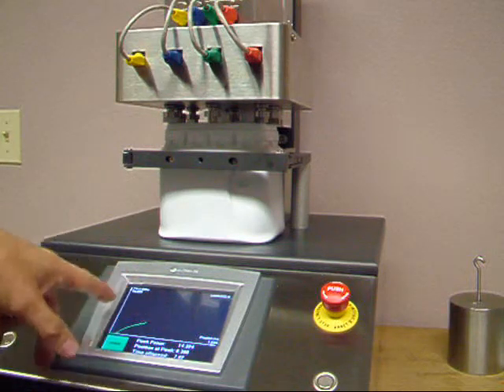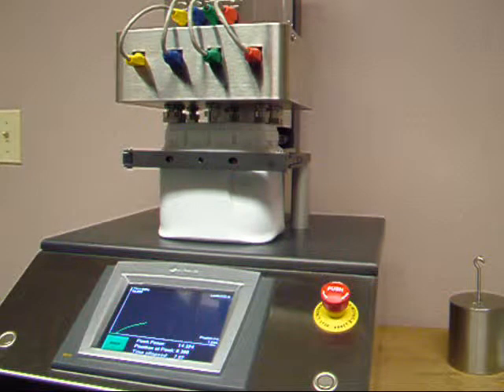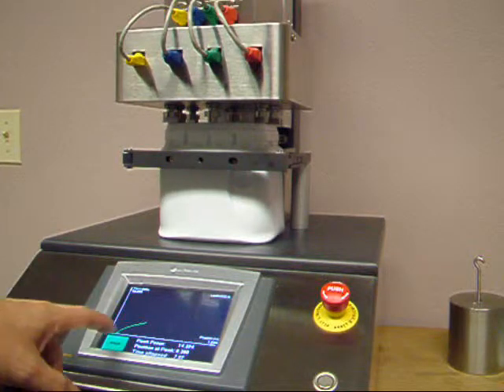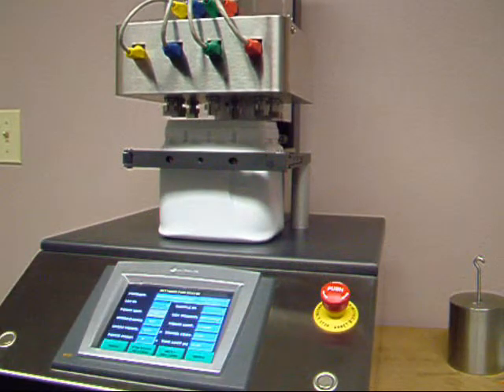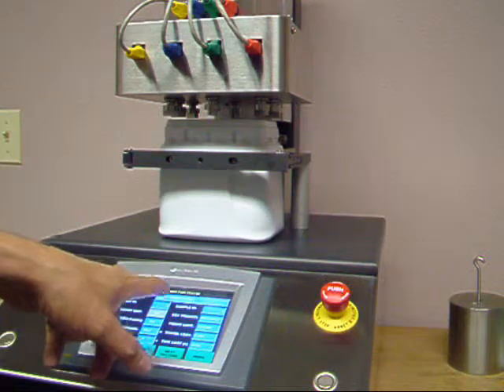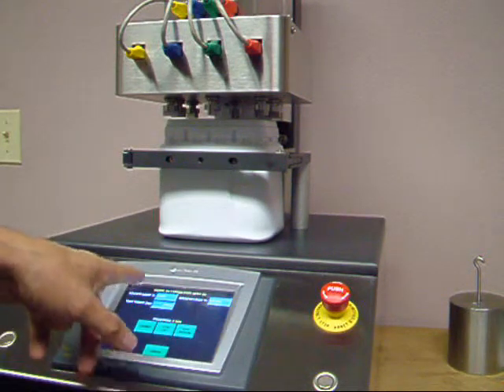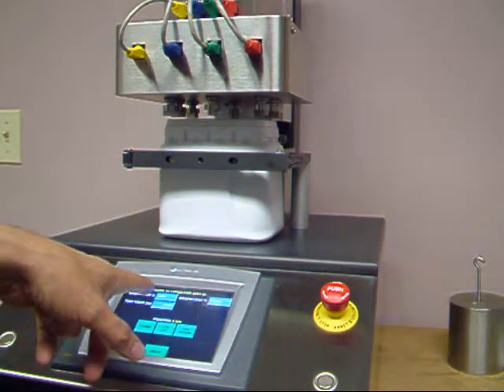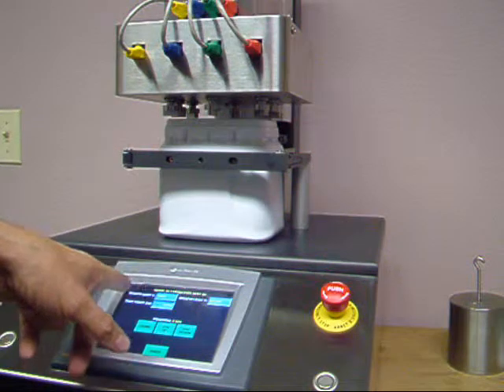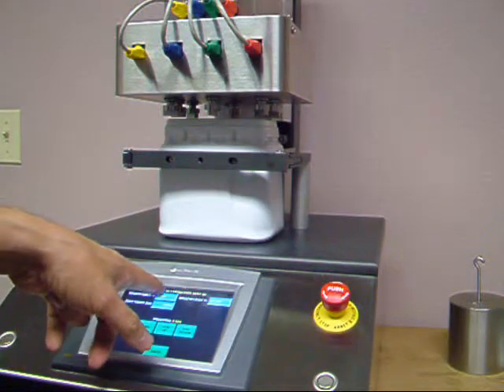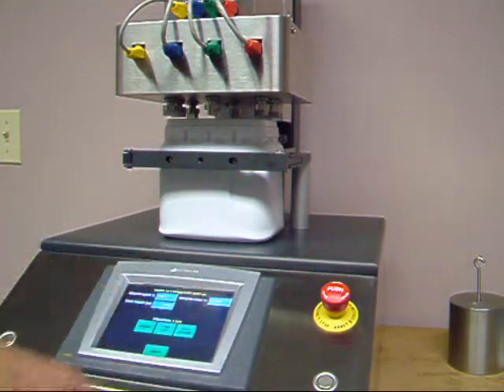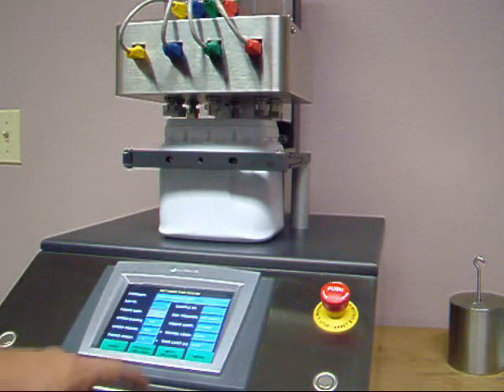The graph is scaled to the graphing limit X and the graphing limit Y variable on the test recipe screen. When you hit the more button and look at the variables on the top, graph limit X is defined as 1 inch, graph limit Y is defined as 50 pounds.